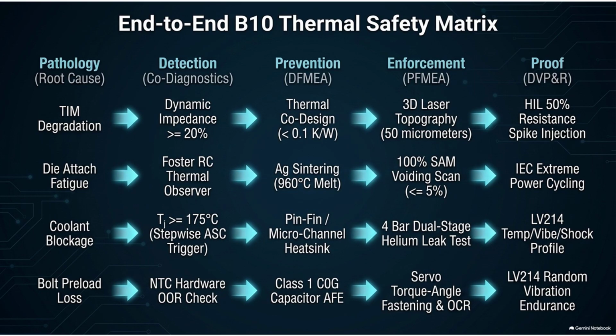And the acceptance criteria are strict. After surviving 200,000 extreme temperature swings, the overall thermal resistance degradation of the system must be less than or equal to 10%. The voltage drop shift across the chips must be less than 5%. And they verify it. Right. They don't just take the computer's word for it. They pull it off the bench and run it back through the acoustic microscope to prove there is exactly 0% delamination in the silver layer.